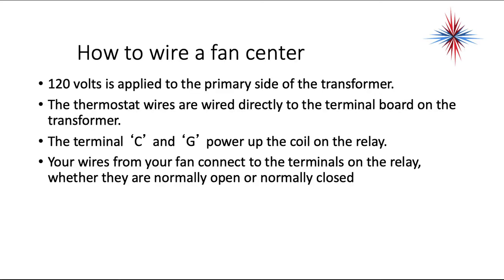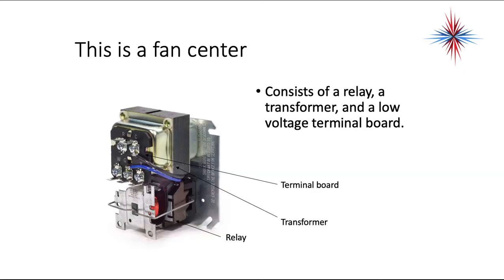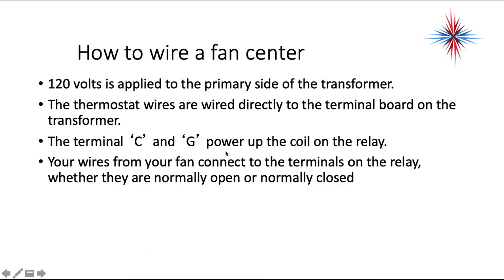120 volts is applied to the primary of the transformer. Those wires are usually hanging off here on the back. This is designed to mount on a square wiring box. The thermostat wires are wired directly to the terminal board on the transformer. The terminal C and G is used to power up the coil on the relay. Your wires from your fan connect to the terminals on the relay, whether they're normally open or normally closed.